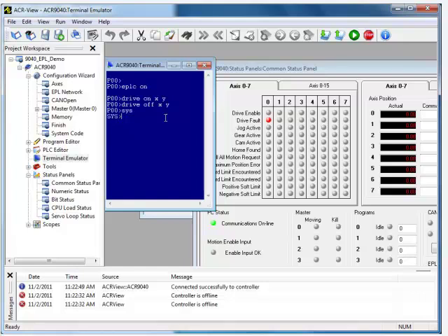From the SYS prompt, if I try to do a DRIVE ON X Y, it'll say unknown command because it doesn't recognize X or Y. But if I do a DRIVE ON axis zero space axis one, both will enable. Same thing with DRIVE OFF. And then I can go back into PROG zero, and back up to the P00 prompt.